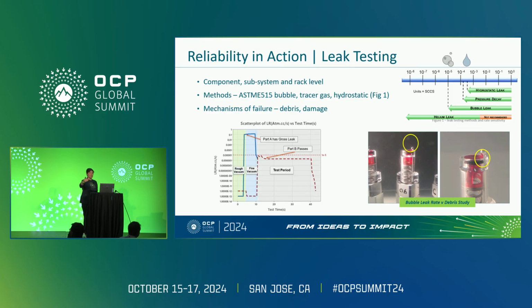On the left-hand side, maybe down to 10 to the minus 4, we're still firmly rooted in viscous laminar flow. When we get past 10 to the negative 6, now it's molecular. I bring that up because it's a nuance in how we might want to correlate those leak rates with a tracer gas like helium back to a fluid leak. And where it gets tricky is when, for example, CPC does helium leak testing on our QDs. We might get a measurement that's 10 to the minus 5th. When I put 100 of those on a manifold, intuitively we say, okay, now my leak rate is 100 times 10 to the minus 5th, or 1 times 10 to the negative 3rd, said another way. And according to this, it should be leaking liquid, and that's just not the case. So there's some logic that we need to apply more accurately.